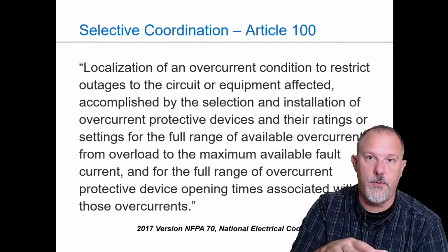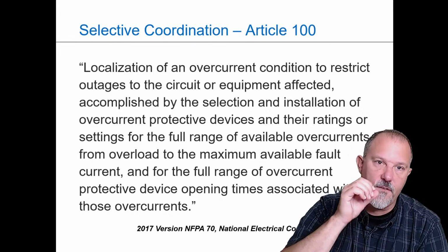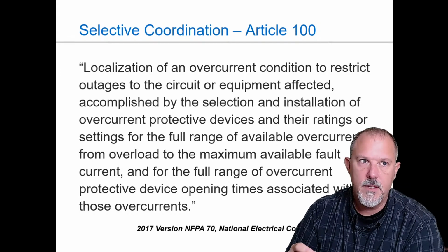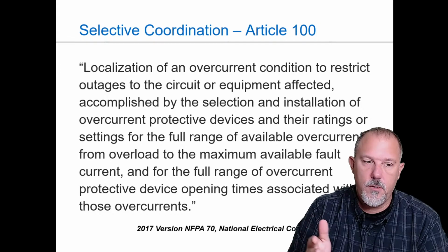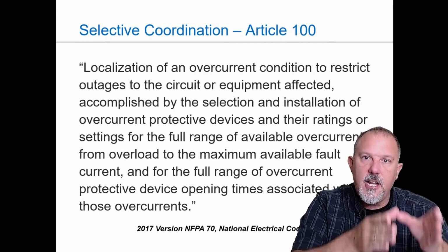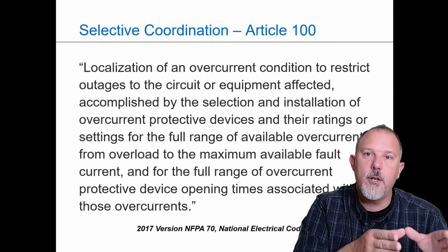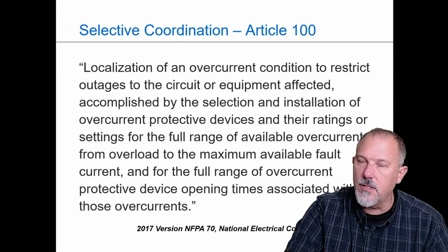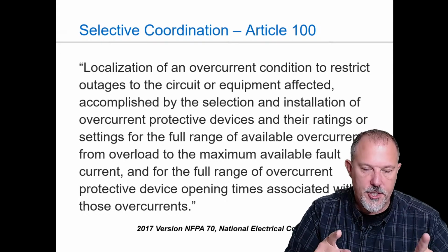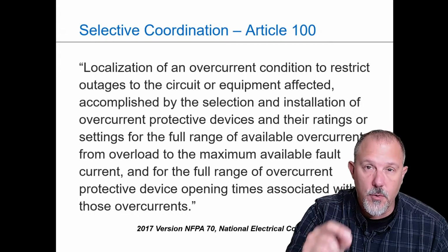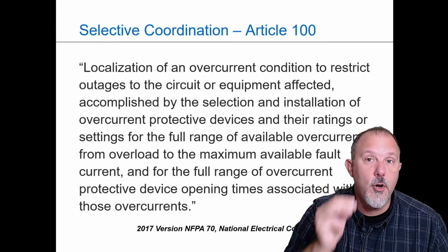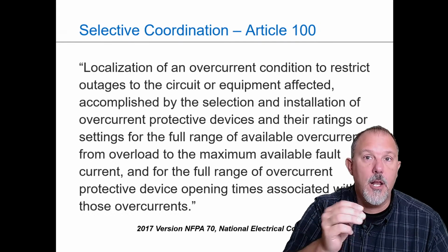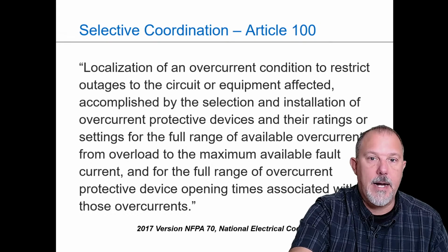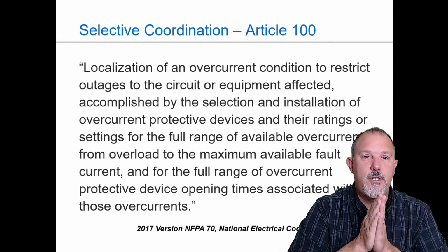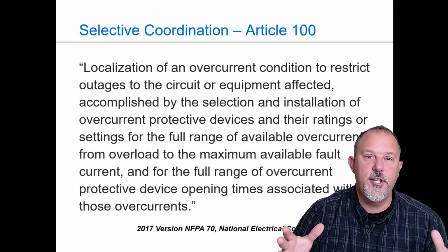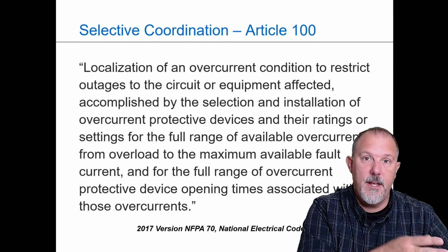And whatever it is I need to do to understand the performance of my overcurrent protective devices, then I need to do it. So that is the basic fundamental principle we cannot lose sight of. Regardless of anything else that we do, ask yourself that question. For an overcurrent condition, which could be a short circuit, a ground fault, or an overload, I want to localize the problem. I don't want to have a widespread outage outside of just taking out the equipment that is affected.